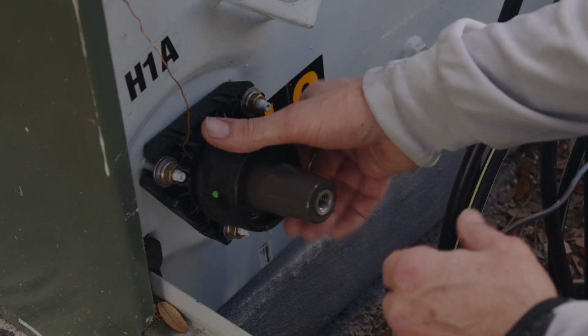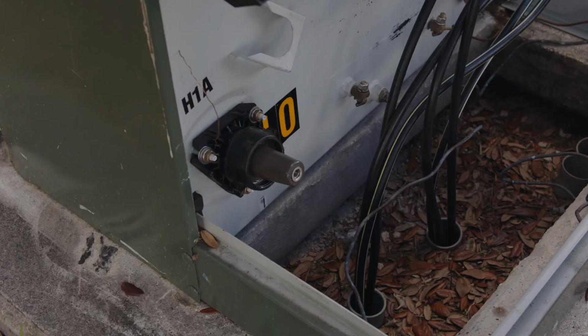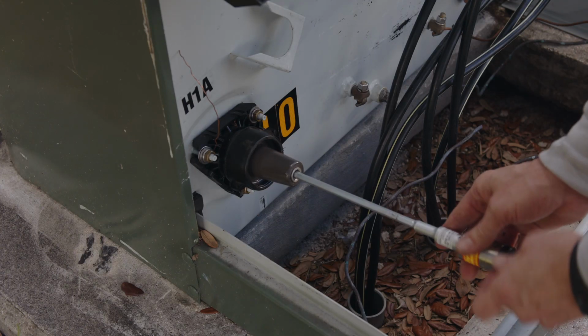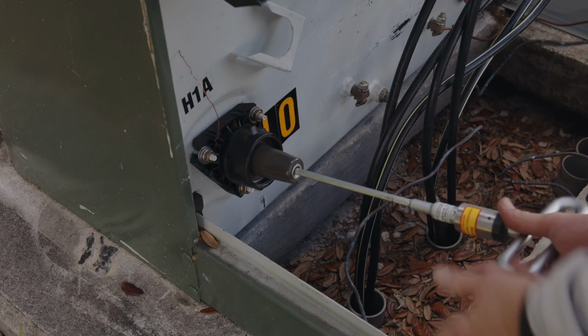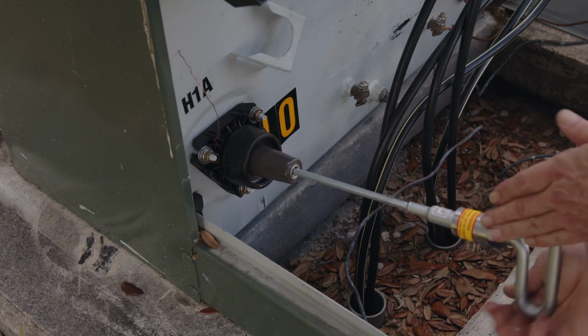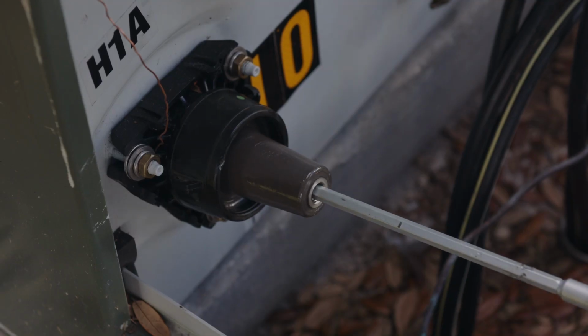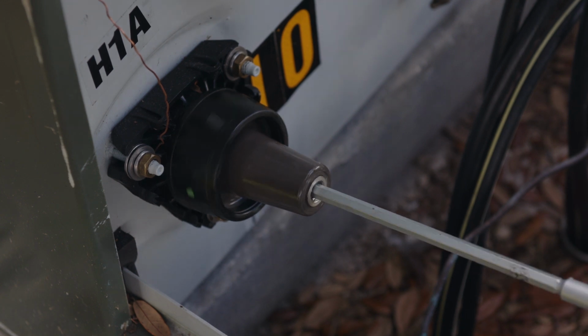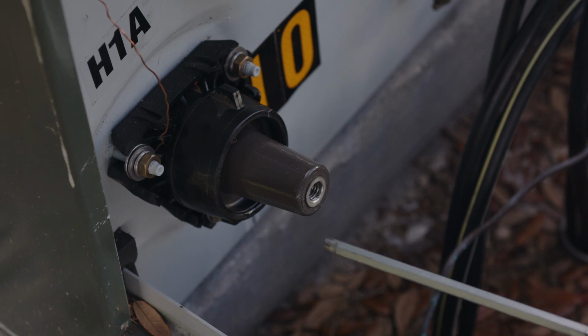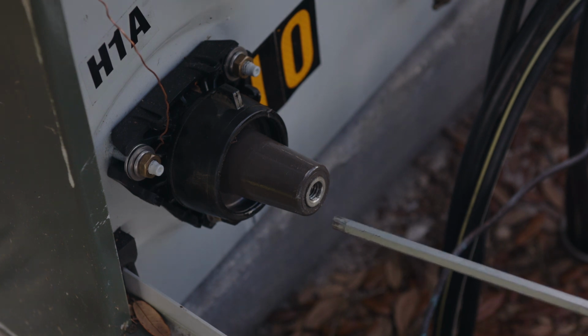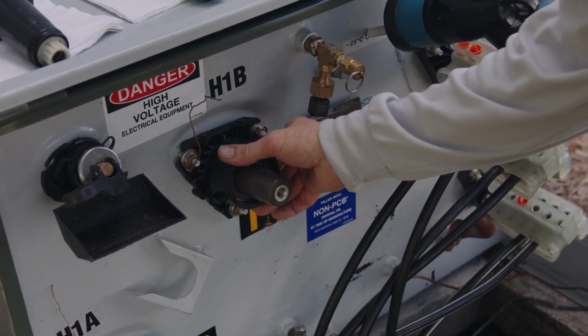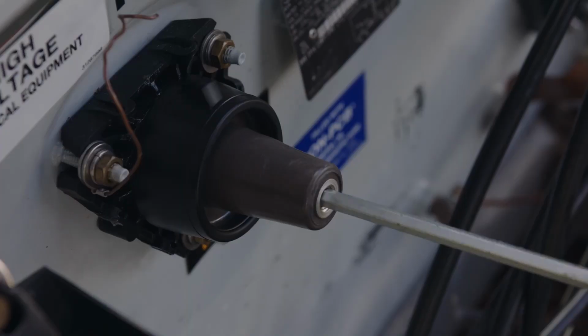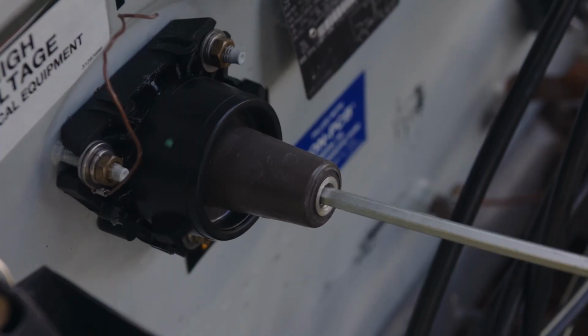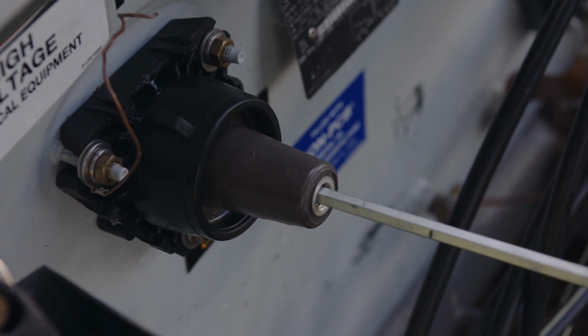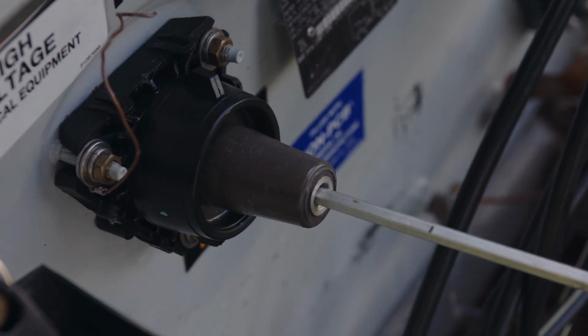Step 5. Install one of the greased bushing well adapters into the H1A bushing well. Torque the bushing well adapter using a bushing well interrupter torque tool. The recommended bushing well interrupter torque tool will make a distinct snap sound when proper torque of 180 inch-pounds is reached. Step 6. Install the remaining bushing well adapter into the H1B bushing well. Torque the bushing well adapter using a bushing well interrupter torque tool.